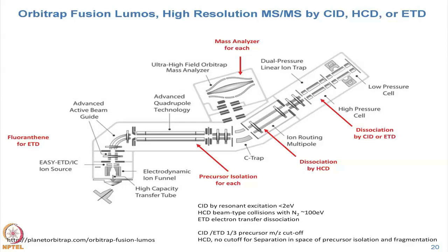This instrument, the Fusion Lumos from Thermo, takes in ions, isolates precursor ions, and then does MS/MS by three different techniques: higher energy collision dissociation (HCD), collision induced dissociation (CID), or electron transfer dissociation (ETD). Spectra can be measured in the Orbitrap at high resolution or in the ion trap at lower resolution but faster speed. In the CPTAC program for proteogenomic data, we generate only HCD spectra and collect mass spectra only in the Orbitrap.